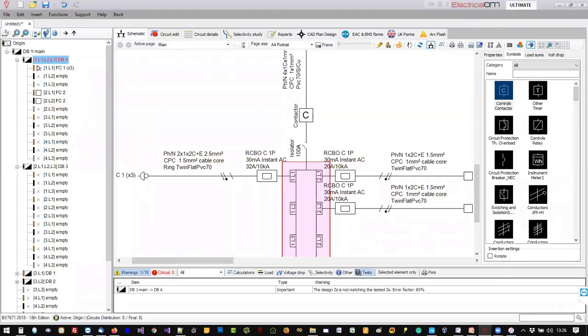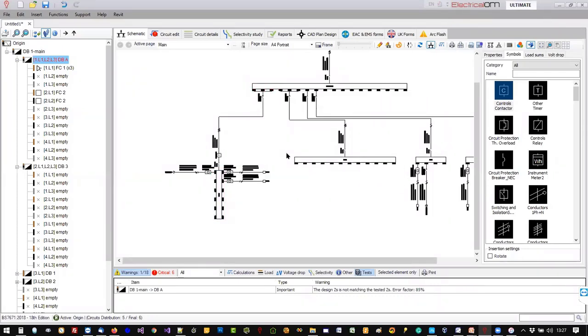We've had a question about flagging certain results and those sorts of things within the report. I think some of the examples here are around insulation resistance as well as those sorts of things. Yeah, there are various developments we're looking at in terms of physical test results coming up in the mobile app. So where there are inconsistencies in R1, R2s, where there are inconsistencies on the Zs, volt drop, these sorts of things, there will be something very similar to the warnings section that we have down here in the core software.